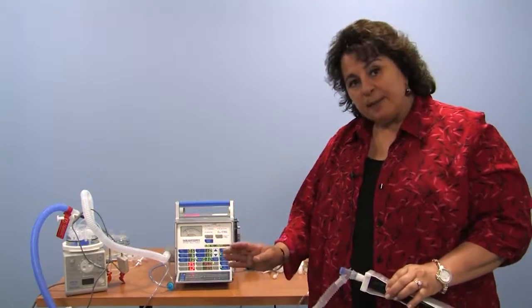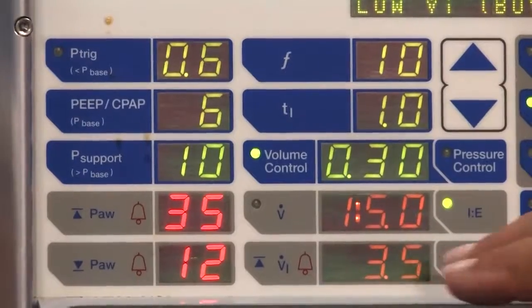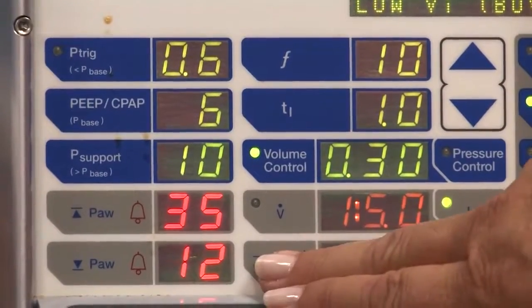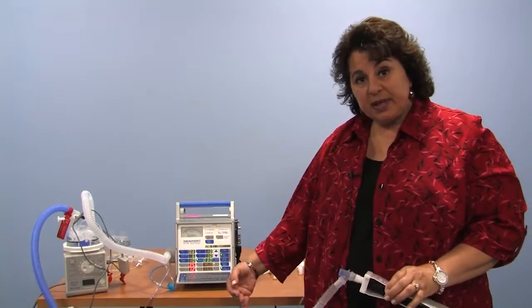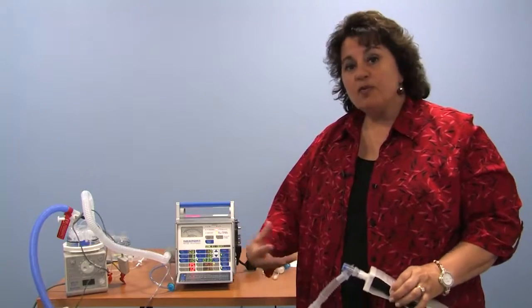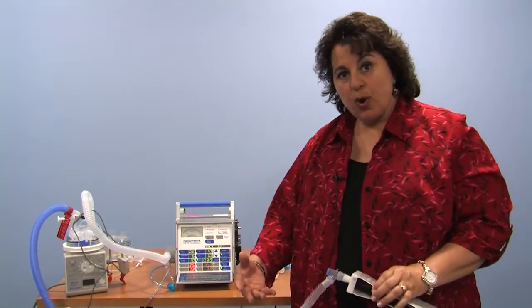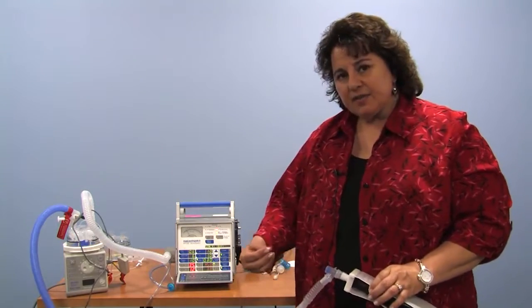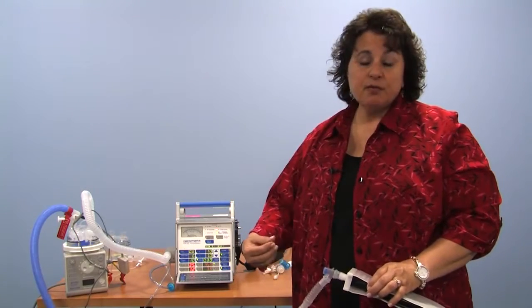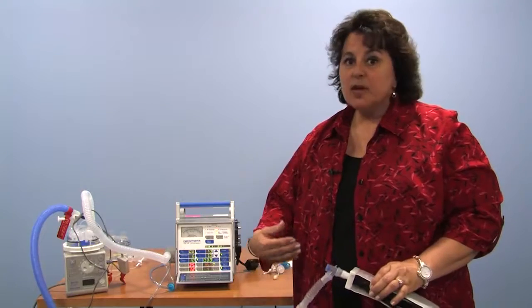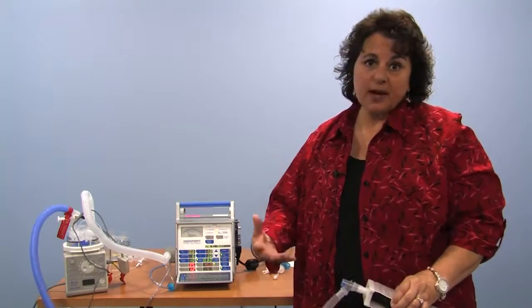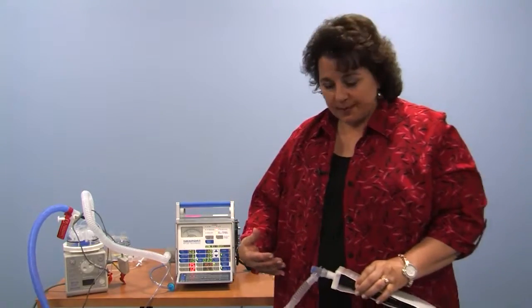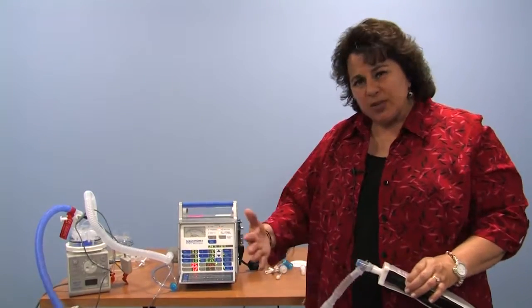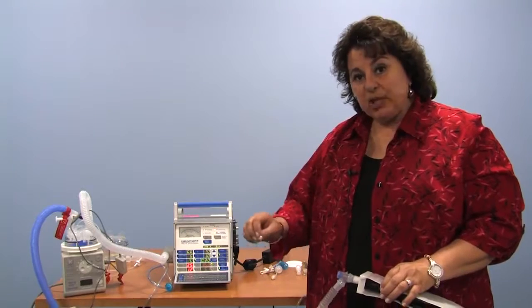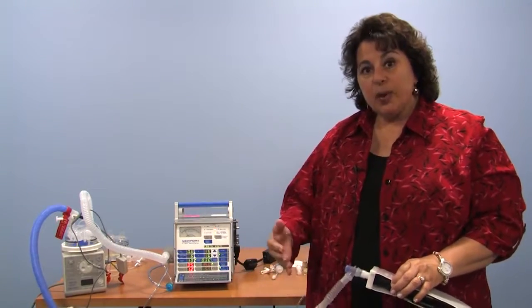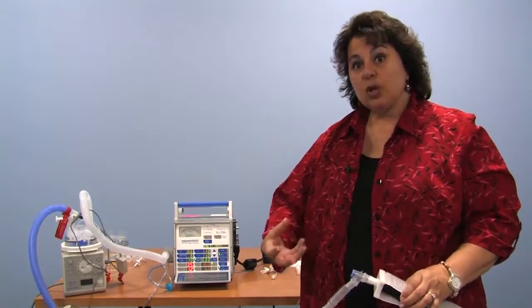We have the low and high minute volume alarm, they call VE. We can observe the minute volume currently. We can also observe the alarms by hitting the button to look at what the high and low are set. The standard would be half and twice what you see your child moving for minute ventilation air. We would set the alarm half and twice that to be safe. If the child has an uncuffed tracheostomy tube or the cuff is deflated, for example during the day for speech, we may need to adjust those alarms. Typically children, when their cuff is down and it's daytime, are attended by other people caring for them who can watch other parameters. You still will have the high and low pressure alarm if you are somewhat disabling the minute volume alarms. We have the BUV, backup ventilation, which you just saw enabled when the child breathed below the amount of air the machine was told to alarm for.